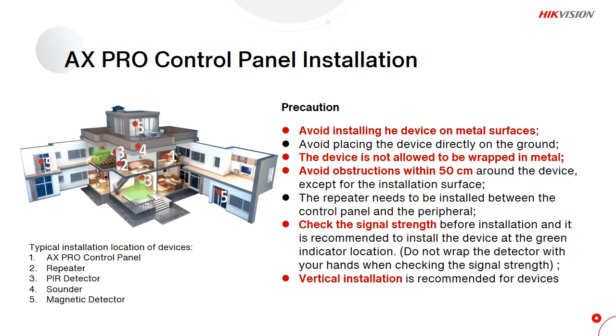Avoid installing the device on metal surfaces. Avoid placing the device directly on the ground. The device is not allowed to be wrapped in metal. Avoid obstructions within 50 centimeters around the device, except for the installation surface.